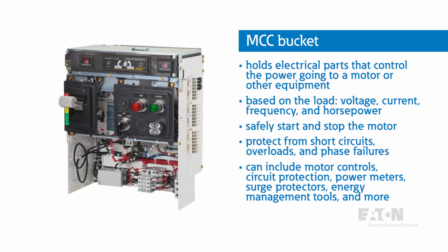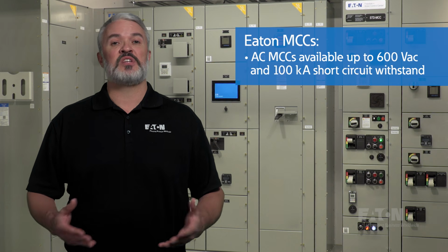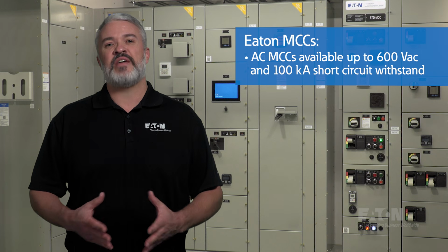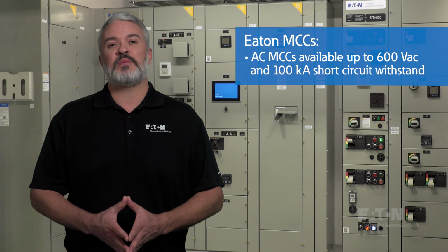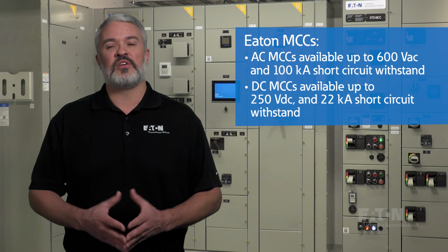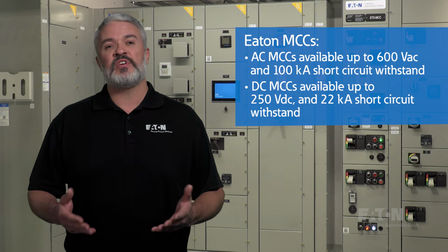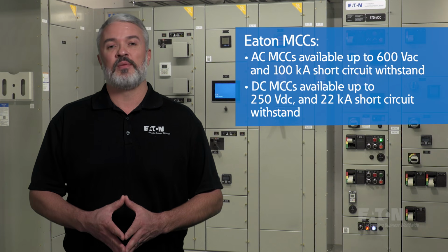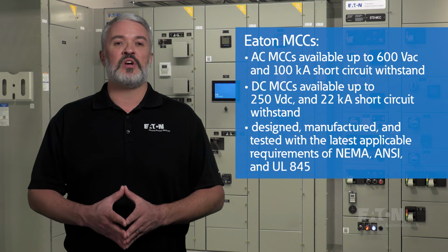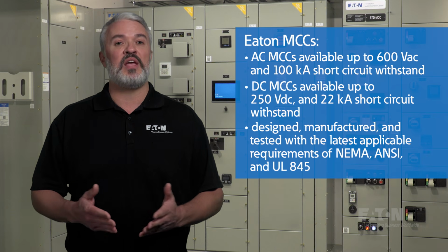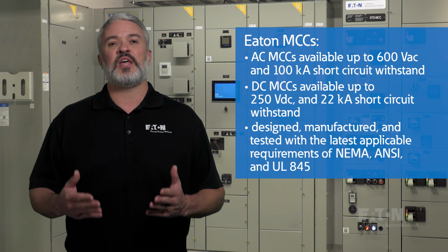A motor starter unit can include different types of motor controls, circuit protection, power meters, surge protectors, energy management tools, and more. Eaton MCCs may be applied on electrical systems up to 600 volts at 50 or 60 hertz, having available fault currents of up to 100,000 amps RMS. DC motor control centers are available up to 250 volts DC, having available fault currents up to 22,000 amps RMS. An ongoing temperature and short circuit design test program, as required by UL 845, ensures a quality product that meets the latest safety codes. Let's go over the details regarding the actual MCC structure and construction.